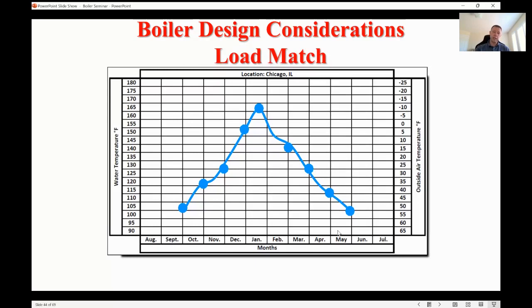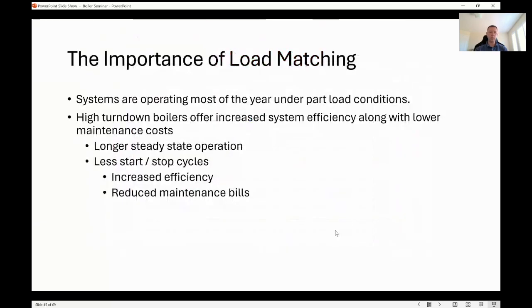So if you take a look here, you turn it on in September, you're always at part load conditions until you hit those few coldest days of the year, whether they're in January and February, that you're operating those design day conditions that you've put all your effort into adhering to. Of course, then you go over that, it gets warmer, but in most areas of Canada we're still running those boilers until June. So that's a good chunk of the year. And you can pick up a ton of efficiency by taking these part loads, most of that year, into consideration. And that's really where turn down ratio comes in to help you out.